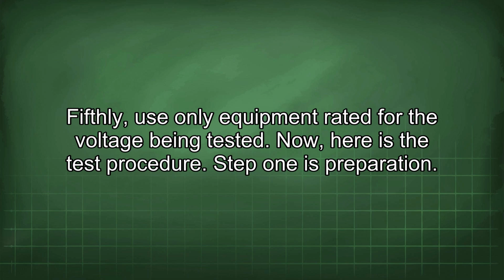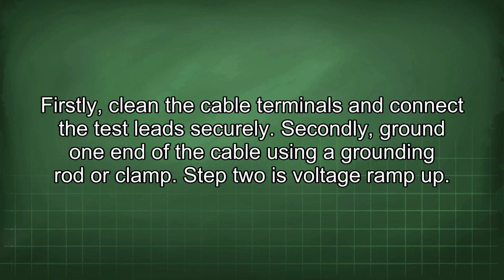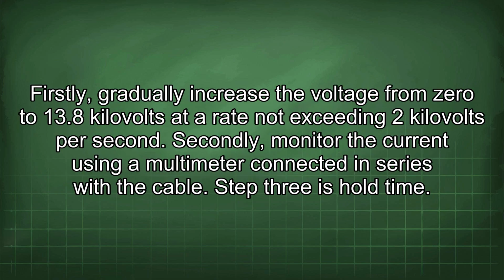Now here is the test procedure. Step 1 is preparation. Firstly, clean the cable terminals and connect the test leads securely. Secondly, ground one end of the cable using a grounding rod or clamp. Step 2 is voltage ramp up. Firstly, gradually increase the voltage from 0 to 13.8 kV at a rate not exceeding 2 kV per second. Secondly, monitor the current using a multimeter connected in series with the cable.